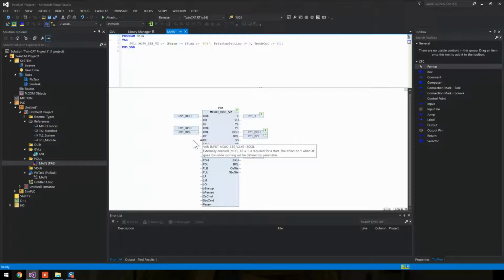And this one, we should also have a separate, maybe a switch for the pumps, so that if the supply voltage is actually supplied, then this one is true. So if you have a relay with a binary feedback, this one should be connected there. So you don't try to turn on or off pumps that are never going to be turned on. And you can indicate it on the HMI display that it's not enabled, so you know where to go to fix the problem.